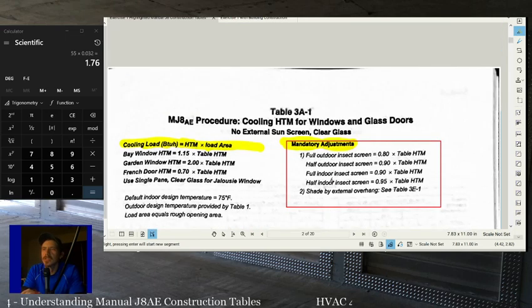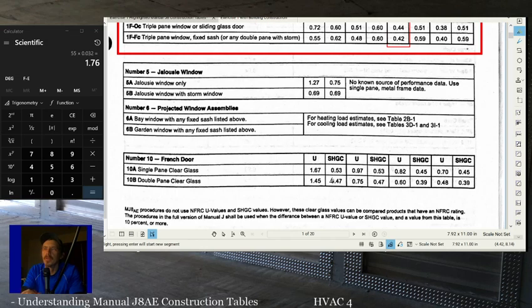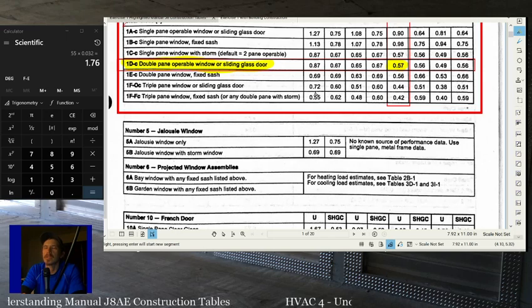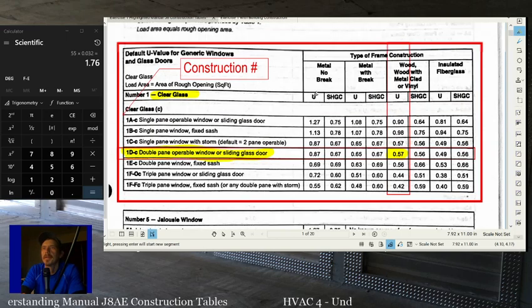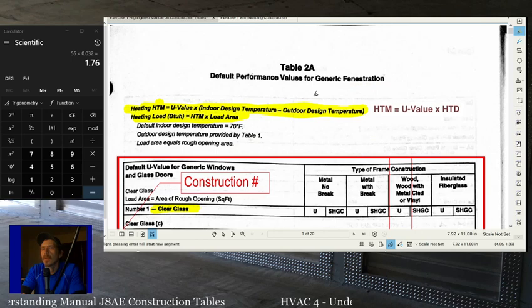Most of the changes in J8 from J7 were made to account for more energy efficient homes. So typically, your loads will be close between the two methods, but a Manual J8 load will usually end up with a smaller system than the J7 loads used to do, except for when you have poor ductwork, and then it shoots that number right back up. So taking ductwork considerations into account is extremely important with J8.